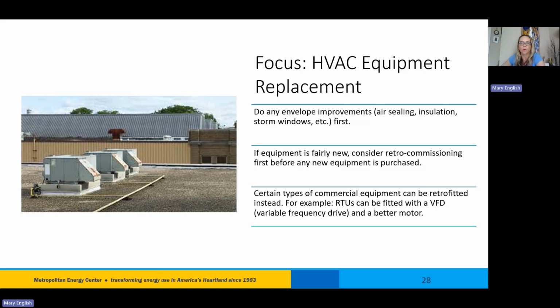Do any envelope improvements first—air sealing, insulation, installing storm windows. That way you'll be replacing a system that's perhaps smaller, cheaper to buy, and cheaper to operate, and it'll be sized correctly based on the added insulation and air sealing and other energy efficiency attributes you added to your building. If the equipment is fairly new, under 20 years old for a commercial system, and has been well maintained, you might want to consider retro-commissioning first before you go replace the equipment—see if it can just be improved and updated with a few tweaks here and there.